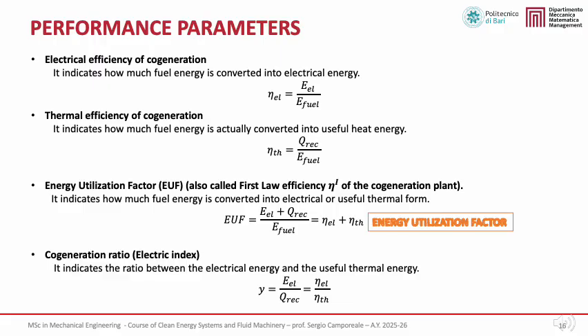We then define the thermal efficiency of cogeneration, which quantifies the fraction of fuel energy that is converted into useful recovered heat. It is important to note that only the heat effectively recovered and delivered to users, Q-rec, is considered, while dissipated heat is excluded. By combining these two contributions, we obtain the energy utilization factor, or EUF, also referred to as the first law efficiency of the cogeneration plant.